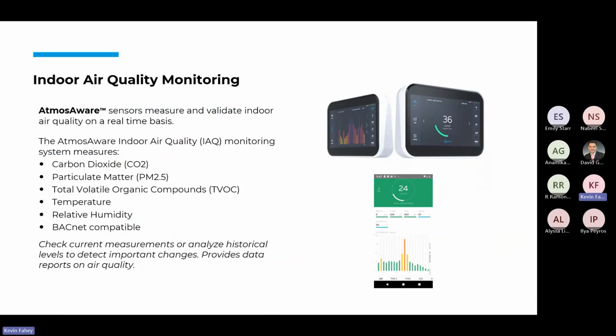So the AtmosAware has a display screen. It measures 5 parameters of air quality: carbon dioxide, particulates that are 2.5 microns and smaller, volatile organic compounds, temperature, and relative humidity. So it measures them in real time, and every minute it's sending information. You can get this information sent to your BMS or BAS through BACnet IP, or you can send it to the cloud, and there's a dashboard that you get with the sensor that will show in real time what the air quality is, and it also trends the air quality.